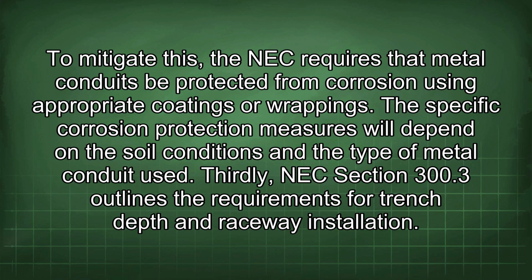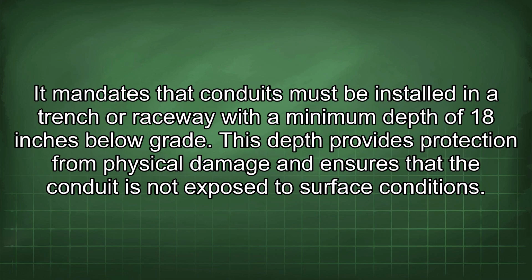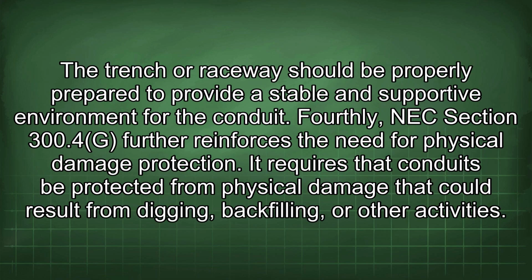Thirdly, NEC Section 300.3 outlines the requirements for trench depth and raceway installation. It mandates that conduits must be installed in a trench or raceway with a minimum depth of 18 inches below grade. This depth provides protection from physical damage and ensures that the conduit is not exposed to surface conditions. The trench or raceway should be properly prepared to provide a stable and supportive environment for the conduit.